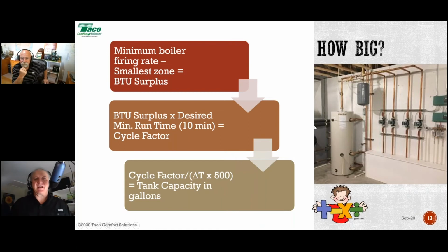Here's how to size it. These are your steps, folks. The first thing you want to find is the minimum boiler firing rate, and then you want to find the BTU load of the smallest zone. So step one is you subtract that BTU load of the smallest zone from the boiler's minimum firing rate.